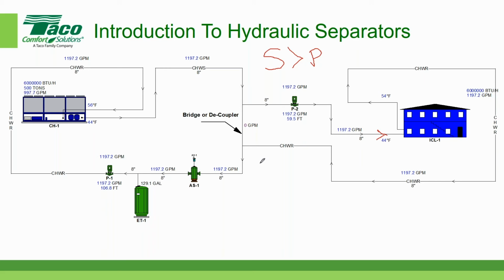So it's important to realize that in a primary-secondary loop, it's not only the flow that gets influenced by the secondary pump, but also the temperature. So in some cases, the temperature will be equal to 44 degrees, and the return water temperature in our case is 56. So if the primary flow is equal to the secondary flow, the chiller is happy, the building is happy. When the primary flow is greater than the secondary flow, the building is happy, but the chiller is not happy. And then if for some reason in the last case, the secondary flow is greater than the primary flow, well, the chiller will be happy, but the building may not be. And that's one of the things that we have to be very careful of.